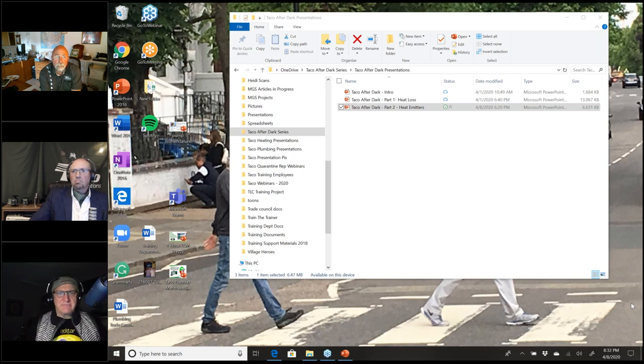But nowadays, based on knowing what that minimum load would be, that smallest zone, we've got equipment on the market that's 10 to 1. We've got equipment that's 15 to 1 for residential applications. And so now just understand what that low fire is, compare that to that smaller load. So I'm not about adding more equipment to a system if it's not required. So you have to do the math and figure it out. Do the math, and then that means add, and don't add when you don't.